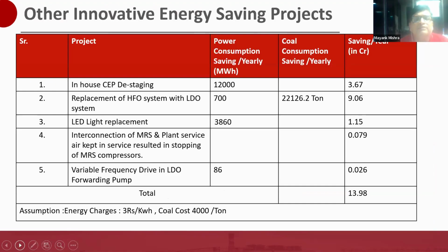These are the various in-house innovative energy saving projects we have done. We also did in-house CEP de-staging, apart from CW de-staging. That de-staging saved approximately 12,000 megawatt hours per annum, estimated at 3.67 crore rupees in savings. We also replaced HFO with LDO system, and replaced boiler lighting with LED throughout the plant. We interconnected the MRS and plant service air, resulting in stopping of MRS compressors, and installed variable frequency drives on the LDO forwarding pump, saving approximately 86 megawatt hours. The total amount of saving is 13.98 crore rupees.